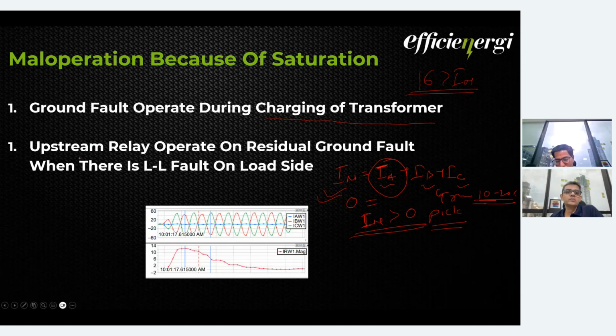So these two cases, I think you must have realized in your projects also, this is happening, that some ground fault is not there, still the relay is operating on a ground fault. The fault is somewhere else, and the relay on the ground fault is operating somewhere else. So these kinds of things can be because of the saturation of the CTs.